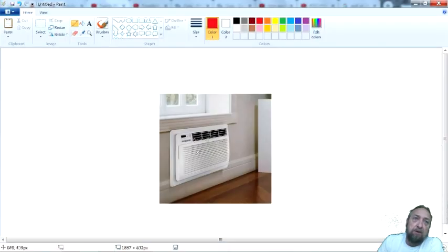And I want to talk about the evaporators here. Right behind it, you have a fan. So air is coming in on these coils. Okay? And then it blows them out here. So as it pulls the air in across the evaporator, and the evap is behind these coils right here, the coils or the evaporator absorbs the heat from the air and the humidity and then blows it out a little bit cooler and a little bit drier than when it came in.